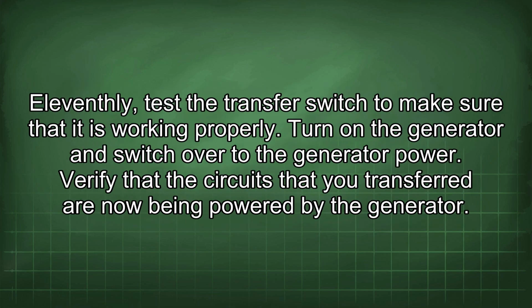11thly, test the transfer switch to make sure that it is working properly. Turn on the generator and switch over to the generator power. Verify that the circuits that you transferred are now being powered by the generator.